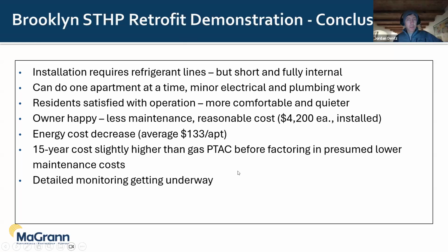And the owner is satisfied with the reduced maintenance. We've got some energy savings, and overall the 15-year total cost to the owner is slightly higher than the gas PTACs, but when you factor in the reduced maintenance, which we haven't calculated in yet, it's probably much lower for the split terminal heat pumps.